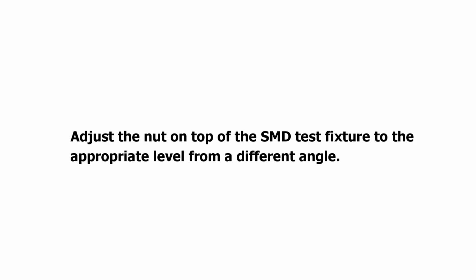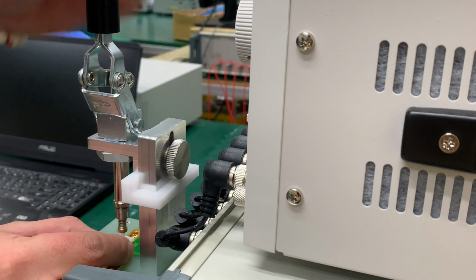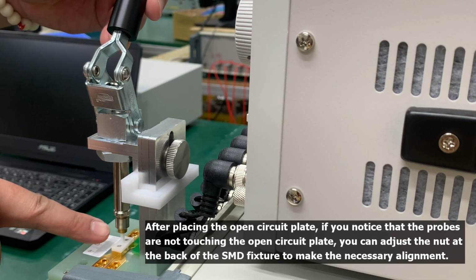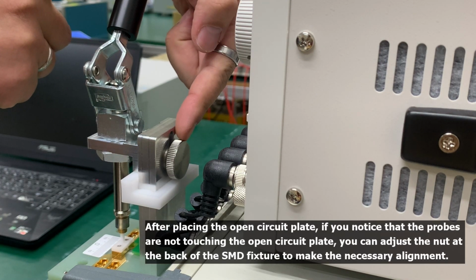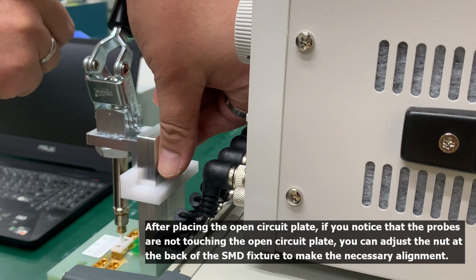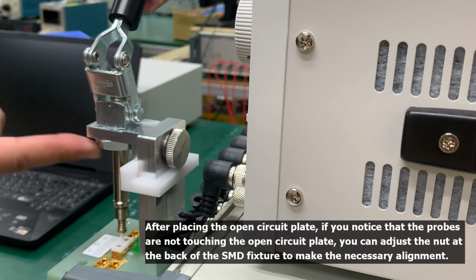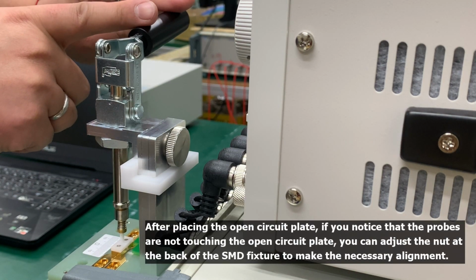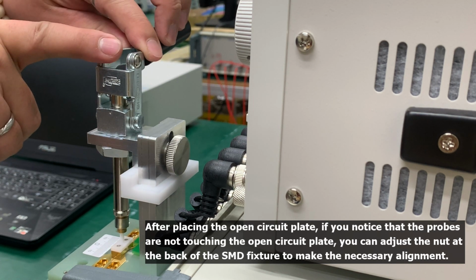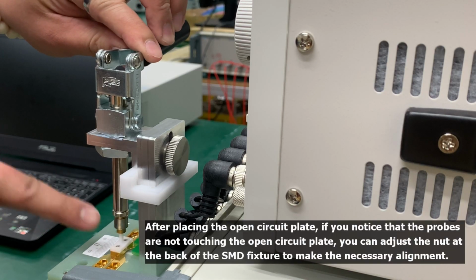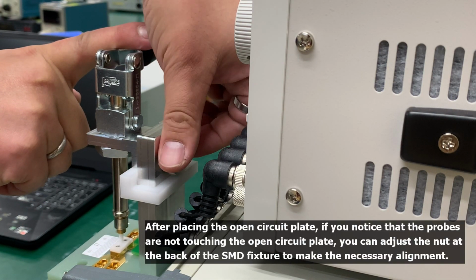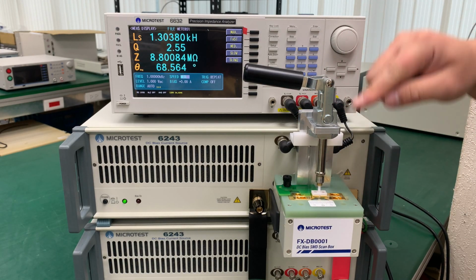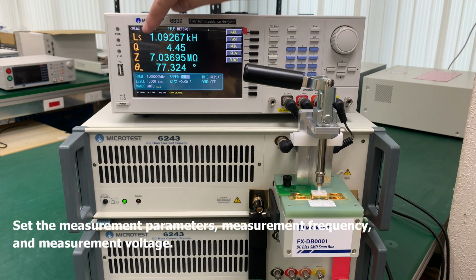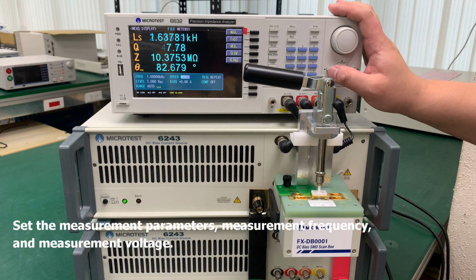Adjust the nut on top of the SMD test fixture to the appropriate level from a different angle. After placing the open circuit plate, if you notice that the probes are not touching the open circuit plate, you can adjust the nut at the back of the SMD fixture to make the necessary alignment. Set the measurement parameters, measurement frequency, and measurement voltage.